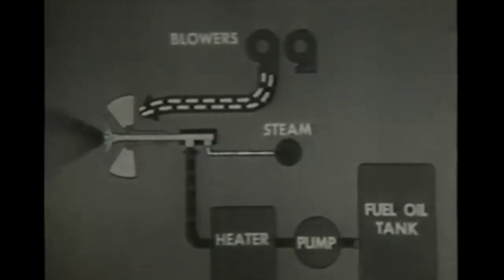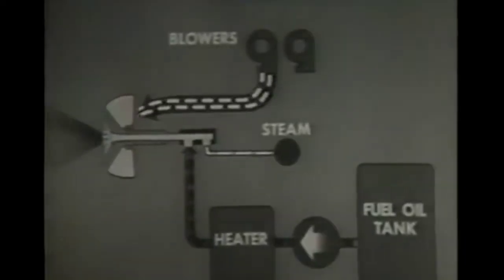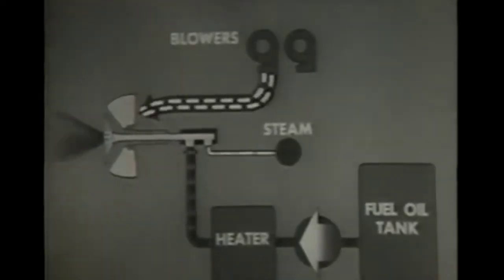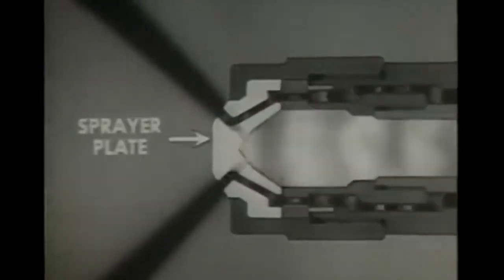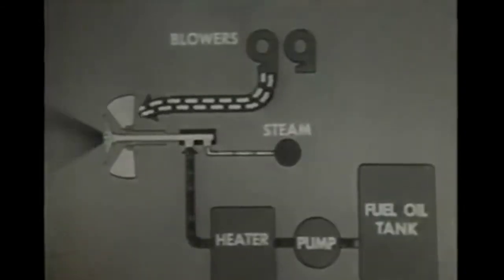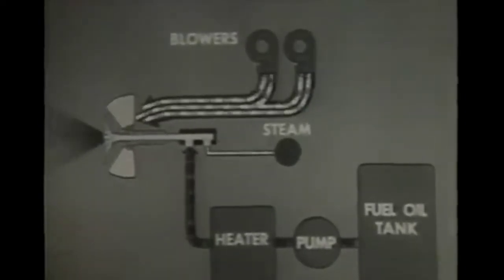Meanwhile, the air from the forced draft blowers is entering the register and mixing with the oil spray. Control of the burner involves regulating the air, oil, and steam supply. Regulate oil pressure to regulate the quantity of oil. When you increase or decrease oil pressure, you must change the steam pressure correspondingly to get good atomization. You must also change the sprayer plate in the burner if the capacity of the plate is incorrect for the new firing rate. As with most burners, you adjust the speed of the blowers and the number in service to control the air supply.